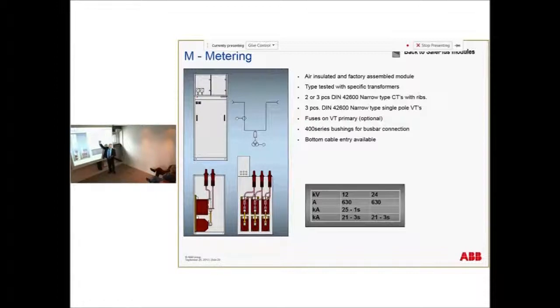In order to sell energy, I think it's the same in Iceland, you need to have class 0.2S. And for the metering panel, we have a standard metering panel where you have the CTs and the VTs. I will also show you some new pickups for voltage and current. But that will of course not have this accuracy. We see a tendency that the more you add new green energy sources, which are normally small energy sources, the more you need to control the load flow in the network. And then you don't really need an expensive metering panel with a high class, but you can manage with the sensors, which I will show you on some of the pictures.